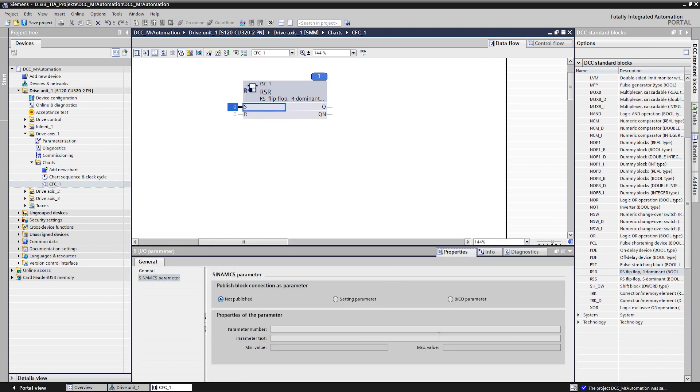In addition, the inputs and outputs can be published as parameters and thus also connected to parameters, the so-called BICOs of the basic system. By selecting the set input and opening the properties window, we can now edit the input. We publish the input as BICO parameter in order to be able to connect it later with the digital input signal of the basic system.